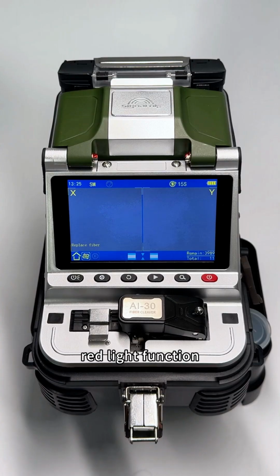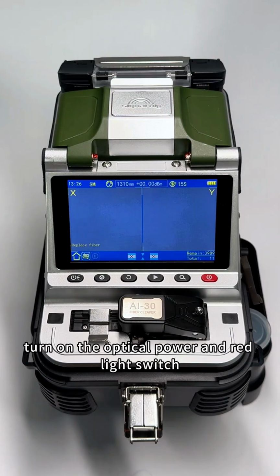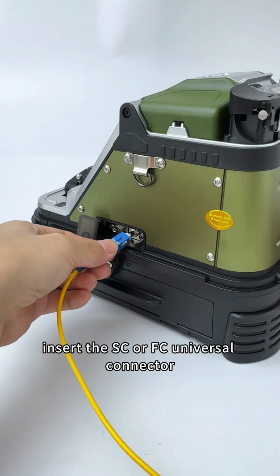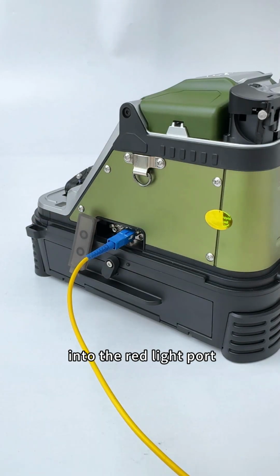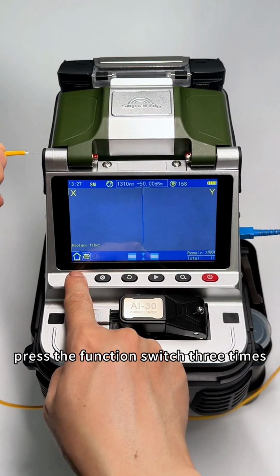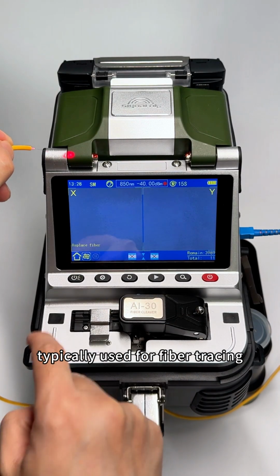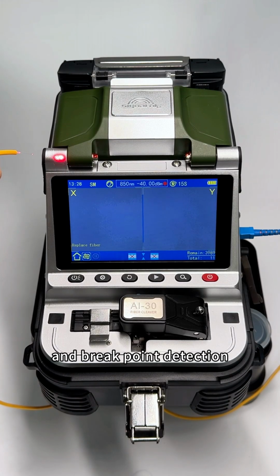Red light function. Enter the splicing interface, turn on the optical power and red light switch. Insert the SC or FC universal connector into the red light port. Press the function switch 3 times to switch to red light mode, typically used for fiber tracing and breakpoint detection.